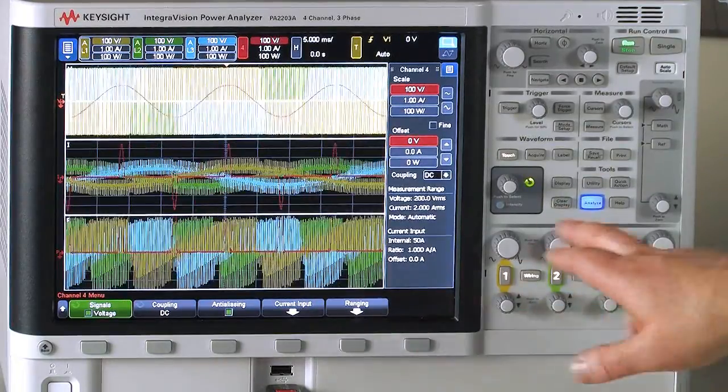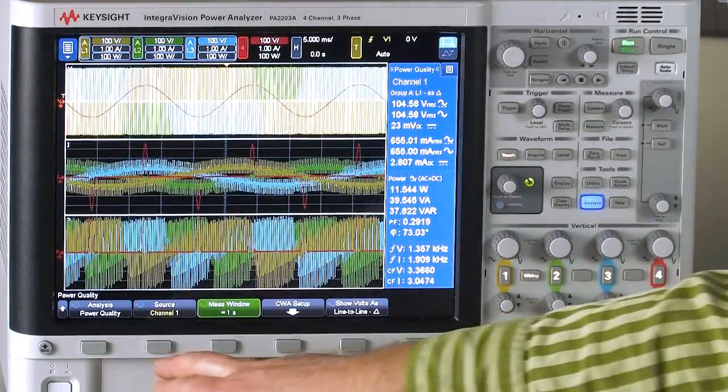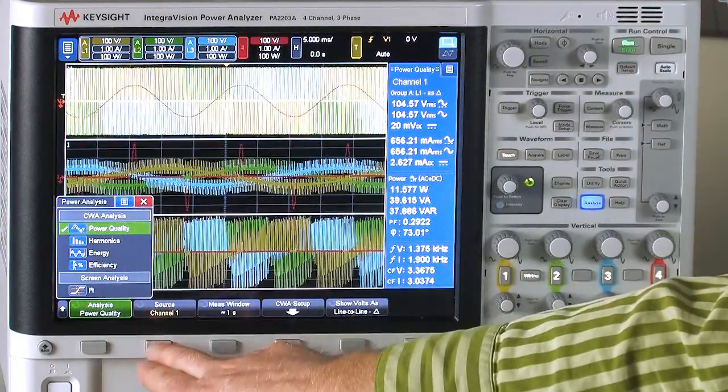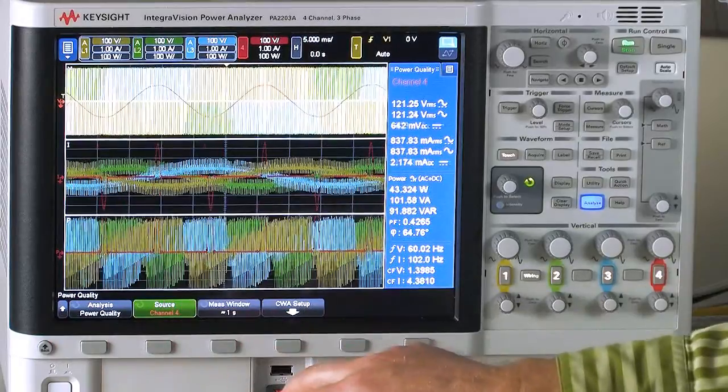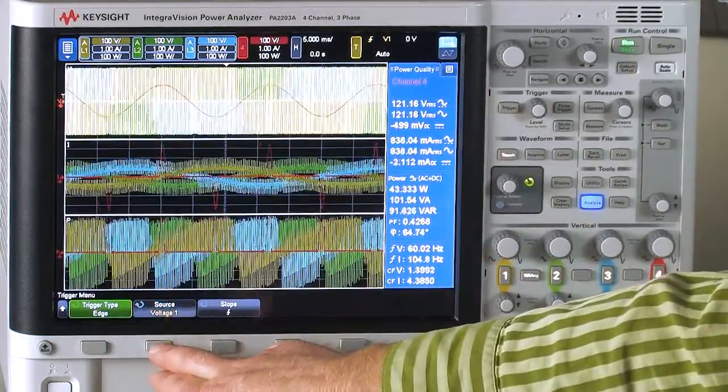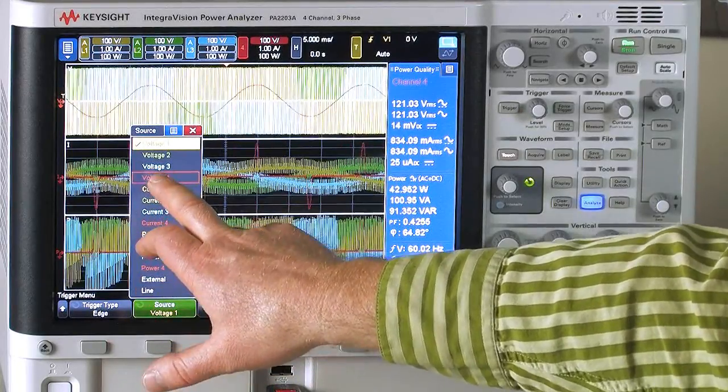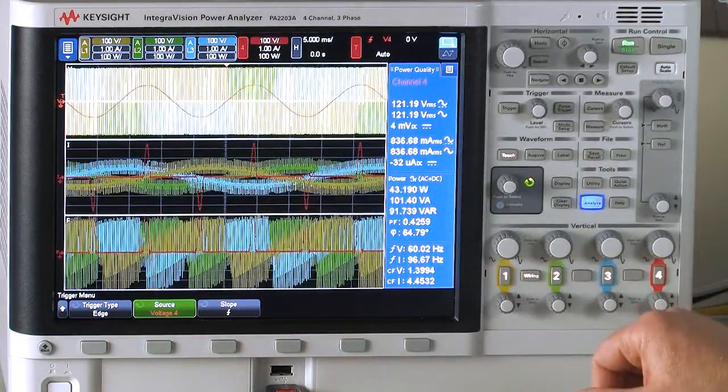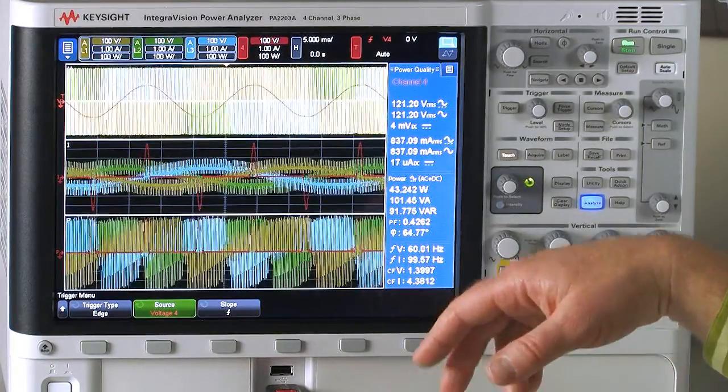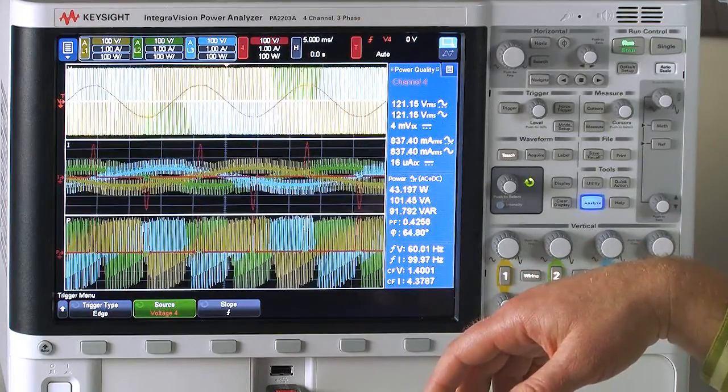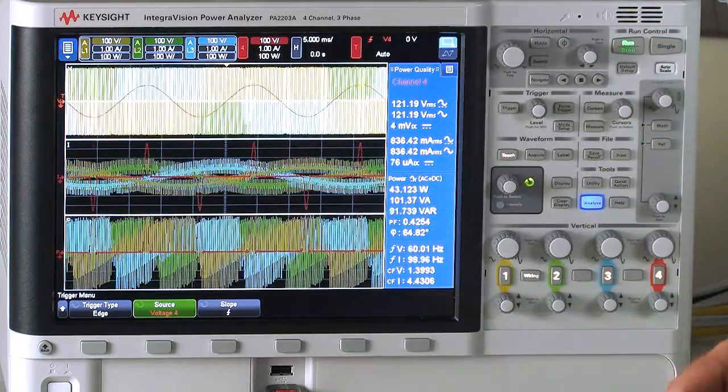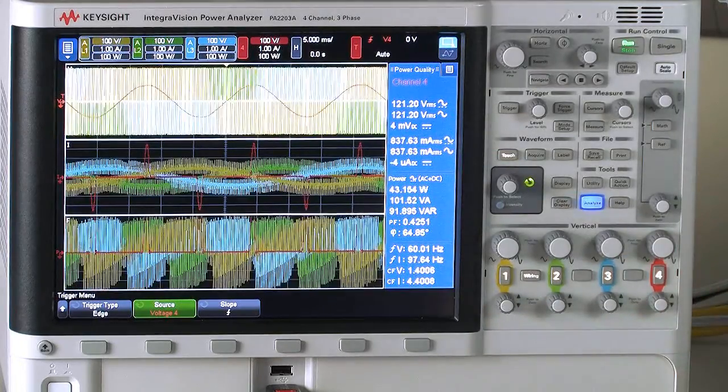And we can actually look at the power quality measurement on that channel and look at what its power factor looks like. I can change my trigger source to channel four. So now you can see the power factor is actually quite poor at 0.4. The angle doesn't really mean anything because it's not a sine wave. It's really a very nonlinear response.